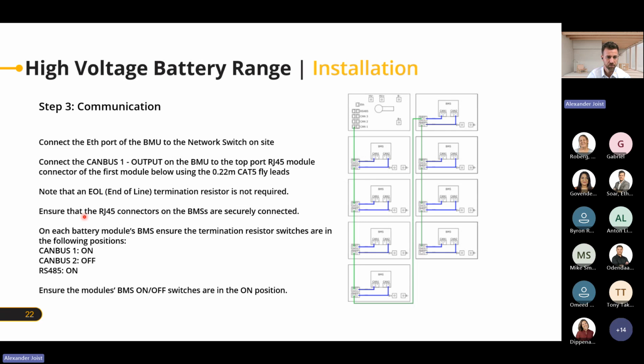Very importantly, for this communication we actually do not need an end-of-line termination resistor. As we said earlier, the termination resistors are on the BMS itself, so what you do is turn CAN bus 1 on, turn CAN bus 2 off, and turn RS485 on. You do these settings on each battery to make sure they're all set correctly, check that, and then switch on all the BMSs — tap that little switch to on, so that all BMSs are switched on.